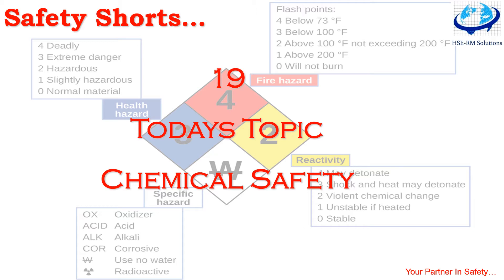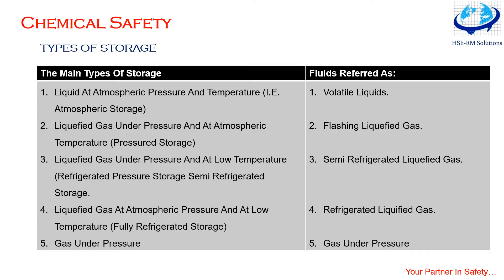Most hazardous chemicals held in storage are flammable liquids and liquefied gases. The code specifies measures to minimize spillage. Vessels and pipework should be of high standard. The number of connections below the liquid level should be kept to a minimum — preferably just one filling or discharge line if possible. Minimum size connections should be used for draining and sampling. Barriers should be provided to protect the vessel against external damage. Measures to control spillage and fire are also available in the codes.